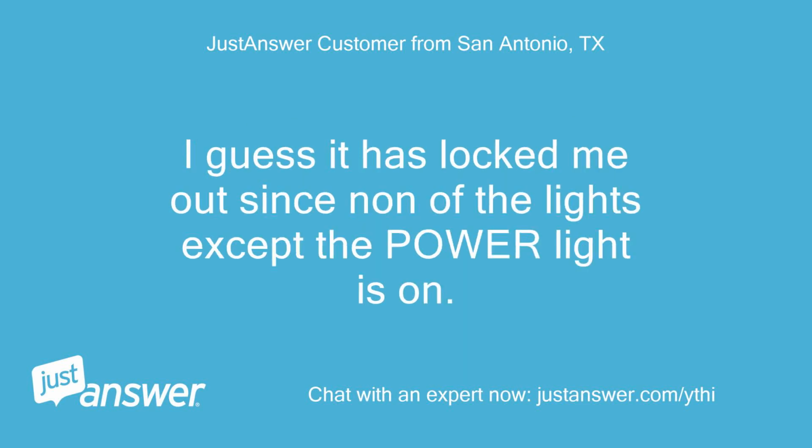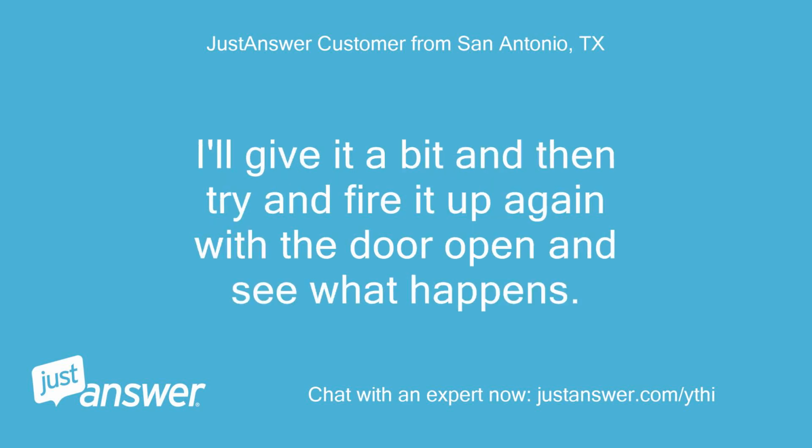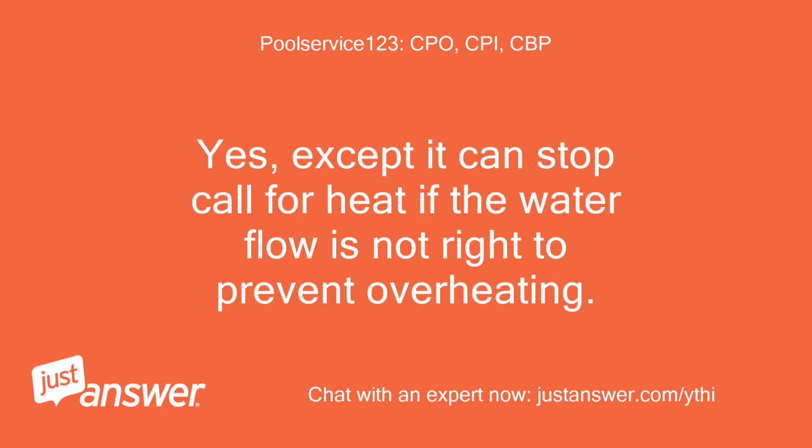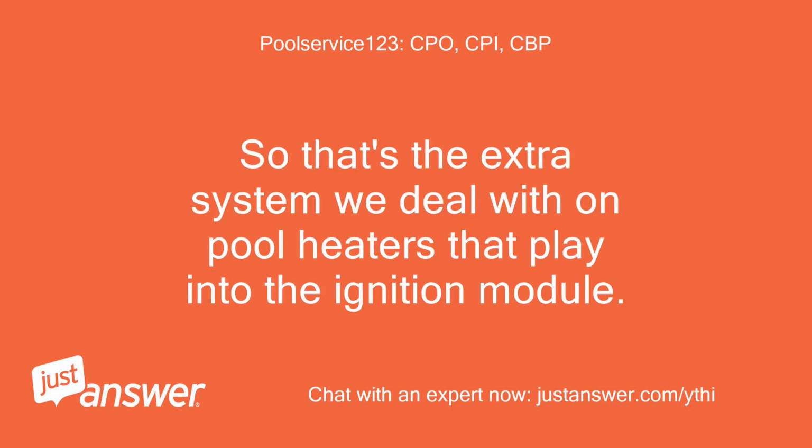I guess it has locked me out since none of the lights except the power light is on. I'll give it a bit and then try and fire it up again with the door open and see what happens. I just had to replace the valve in my gas dryer, so I'm assuming the spa heater works in generally the same manner. Yes, except it can stop call for heat if the water flow is not right to prevent overheating. So that's the extra system we deal with on pool heaters that play into the ignition module.